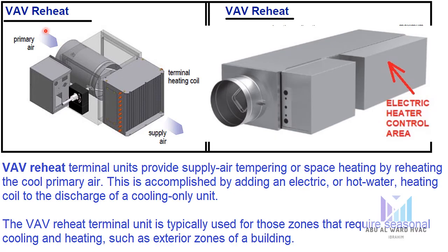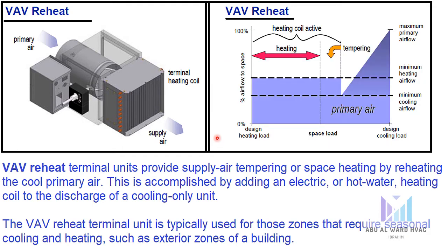VAV Reheat Terminal: A VAV reheat terminal unit provides supply air tempering or space heating by reheating the cool primary air. This is accomplished by adding an electric or hot water heating coil to the discharge of a cooling only unit. The VAV reheat terminal unit is typically used for zones that require seasonal cooling and heating, such as exterior zones of a building. In the cooling mode, the unit is controlled in the same manner as the cooling only unit. The supply airflow is reduced as the cooling load in the space decreases. When the space cooling load drops below the minimum primary airflow setting, the heating coil warms or tempers the primary air to balance the low space cooling load.